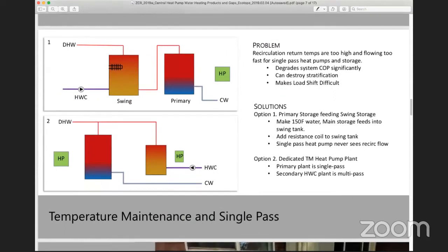So one of the biggest challenges that we've had in about 10 years of working on central heat pump systems is how to deal with the temperature maintenance load, which is just the recirc. One thing that's really frustrating when you get into designing these things, and we've seen a lot of problems in some early designs, is that the recirculation temps are too warm, and so the heat pumps don't have anywhere else to put their heat, and you have to do some things to solve that problem. But this can lead to COP degradation. It can destroy your stratification, and it makes the load shift really difficult.